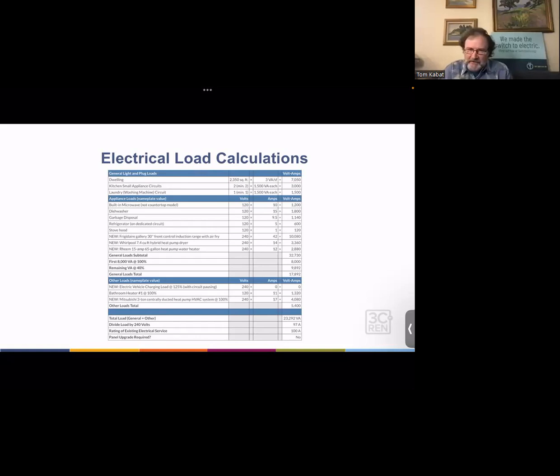Yep, that sounds like a good explanation. I was just putting in the chat too that the code calls these things demand factors, but that's not a very descriptive name, so we call them coincidence factors. It evokes the idea that they're looking at what is generally going to be the coincidence of these things being at their full power need all at the same time at the building peak. The code uses those 40% factors for a lot of it, and in a lot of studies being done by different researchers around the country, we're finding much lower numbers anyway, so these are pretty conservative factors.